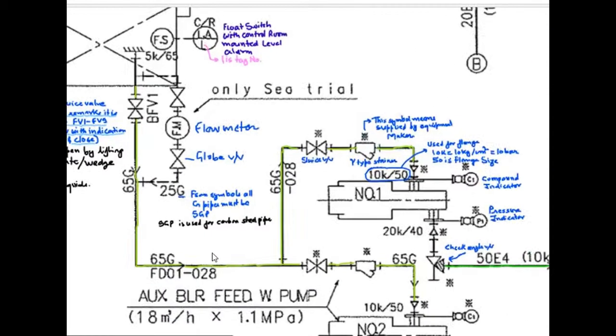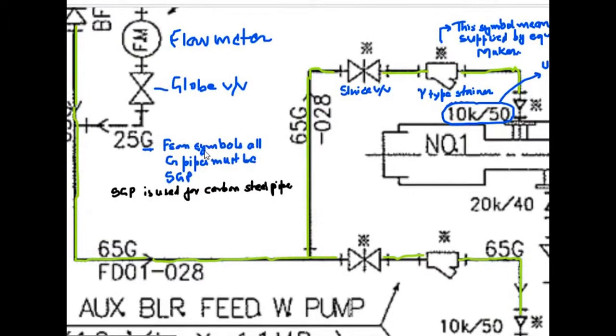Now, one thing is this G means from the symbols given before this drawing, G pipes must be SGP. SGP is used for carbon steel pipes. Wherever you saw G with the piping symbol, it means SGP pipes, carbon steel pipes are used.